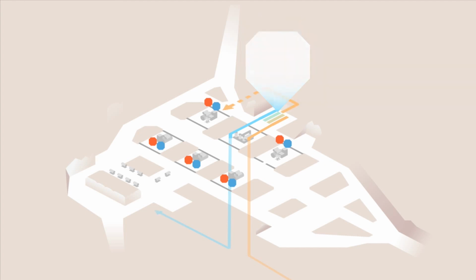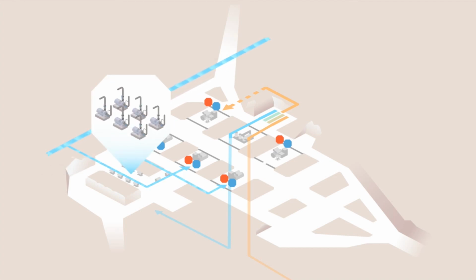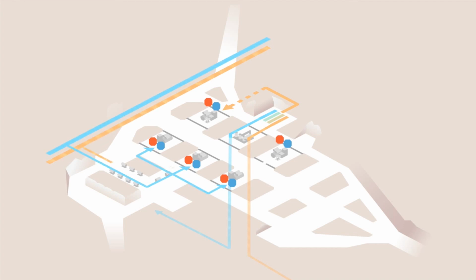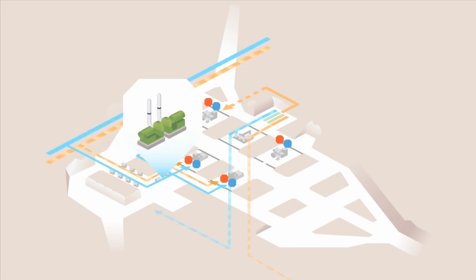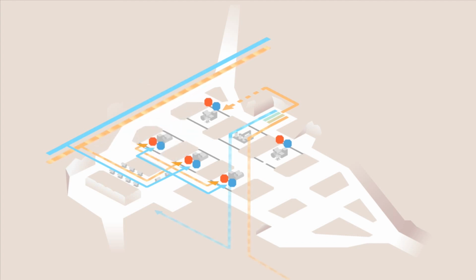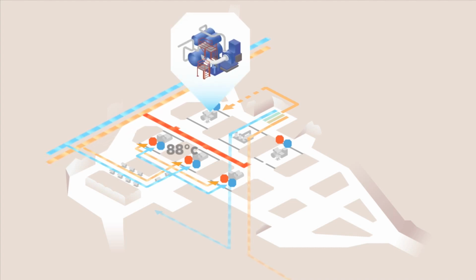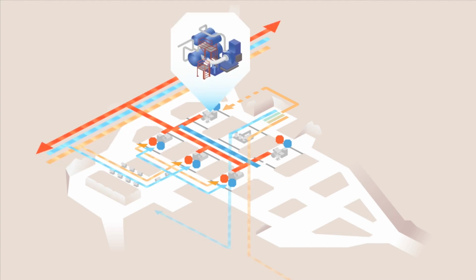The temperature of the return water from the district cooling coming back to the Katrivala plant is between 16 and 18 degrees. This return water is pumped by the district cooling pumps to the heat pumps, where the water is cooled again to about 4 degrees. The temperature of the return water coming back to the Katrivala plant is about 45 degrees. This return water is pumped by the district heating pumps to the heat pumps, where the water is reheated to about 88 degrees. The 5 heat pumps of the plant refine the waste energy into district heat and district cooling in a single process.